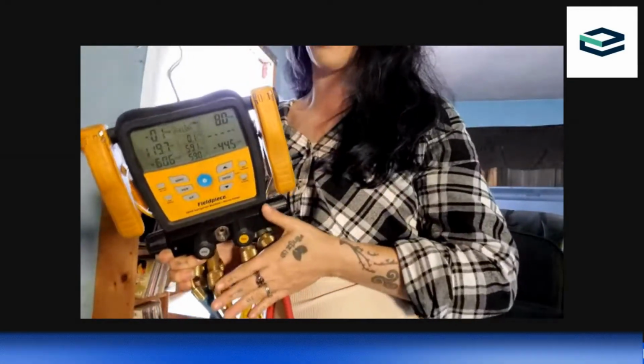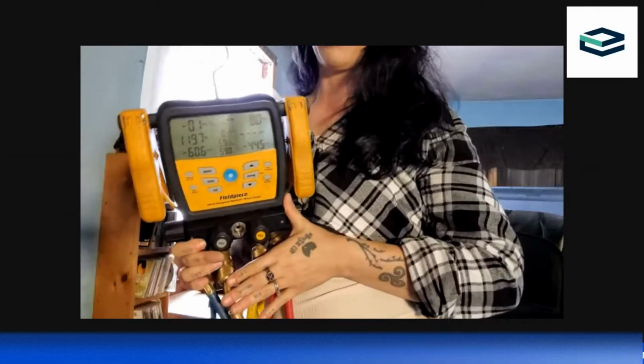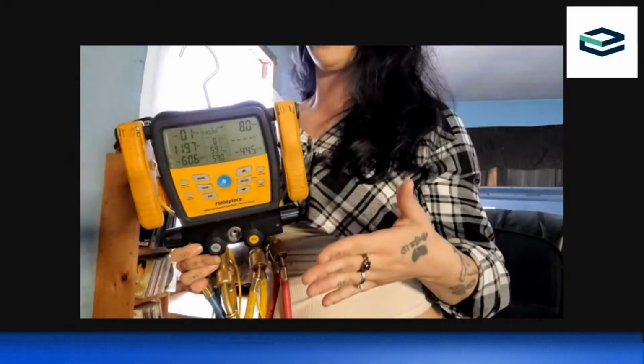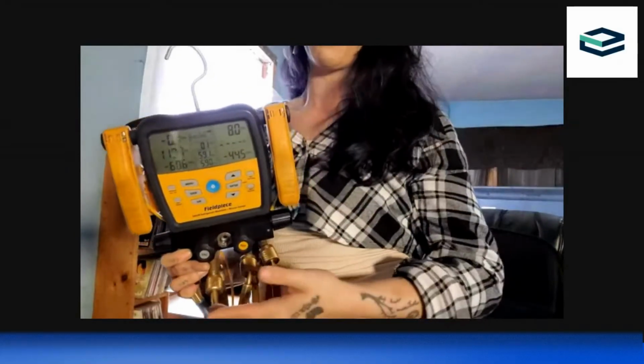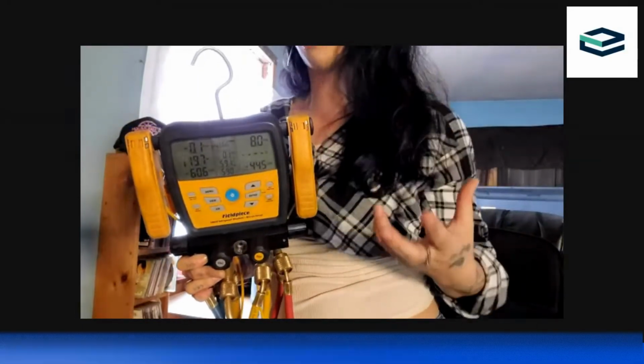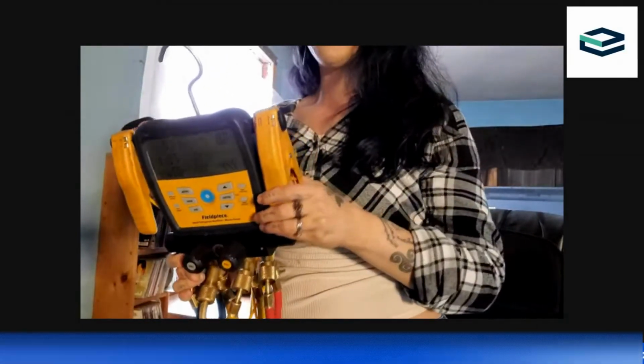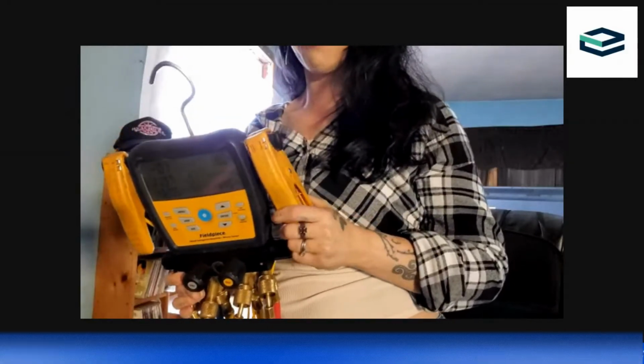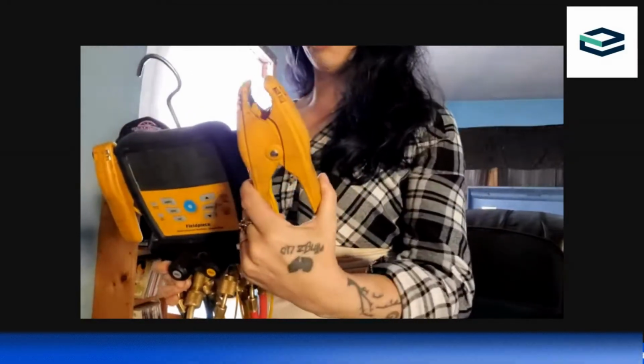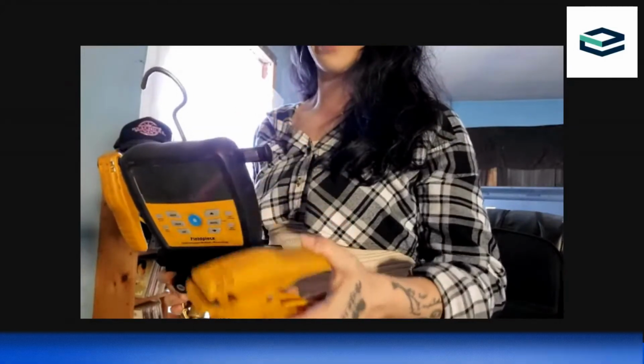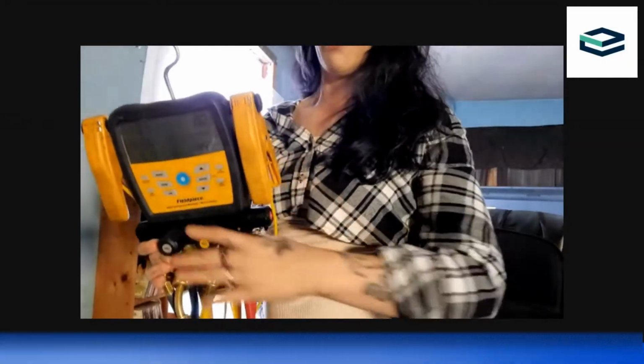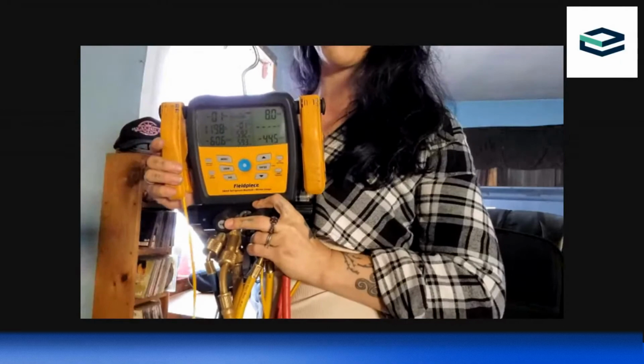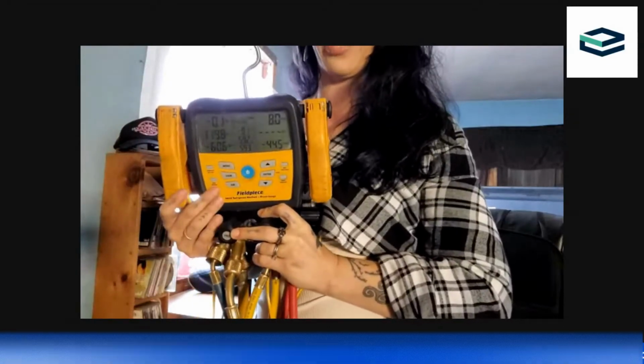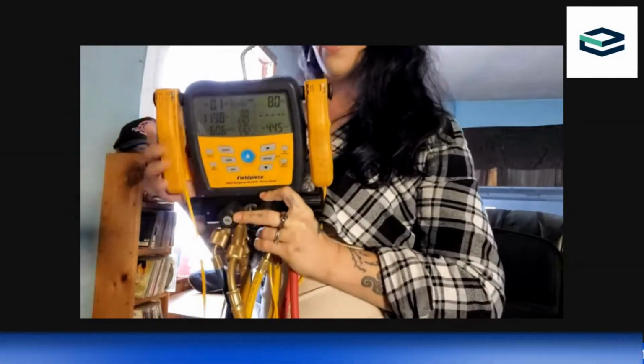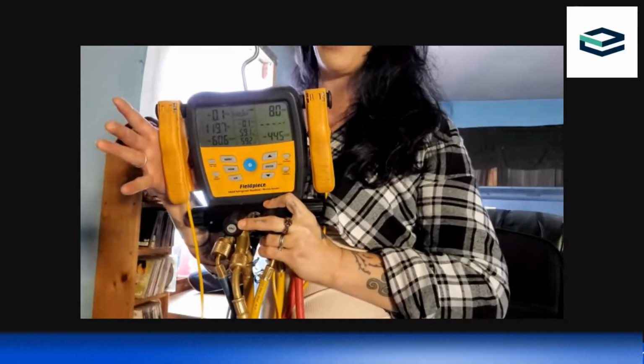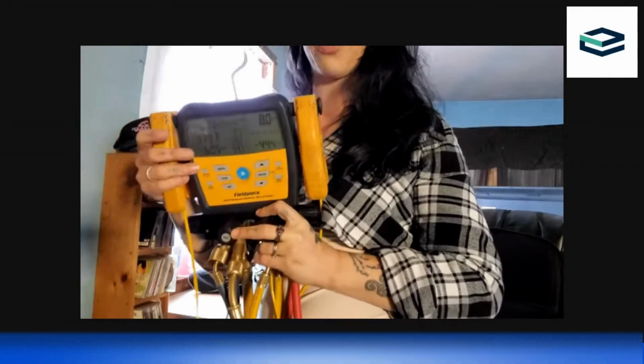When we check pressures, we also need to check temperatures. A lot of the issues that we have in reading what's going on within the refrigeration cycle is that we don't know all of what's going on. So with gauges like these, we can get a more comprehensive view of what's happening. These are temperature clamps. These go on your high side line and your low side lines. And these tell us what our superheat is. This manifold will automatically calculate superheat and subcool, which we'll talk about. And then they also tell us what our temperature differentials and splits are.